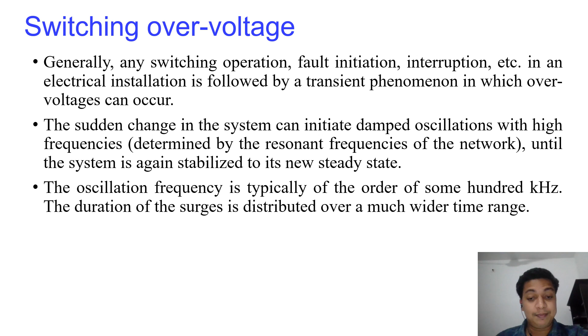And the duration of the surge is situated over a much wider time range, as we will see later. So just like temporary overvoltages, what are the causes here? Temporary overvoltage can occur for some duration of time, but a switching operation is a sudden event, like a fault occurrence. It happens suddenly and will not be sustained for a long time; it is for a small time interval. That is what is meant by switching overvoltage.